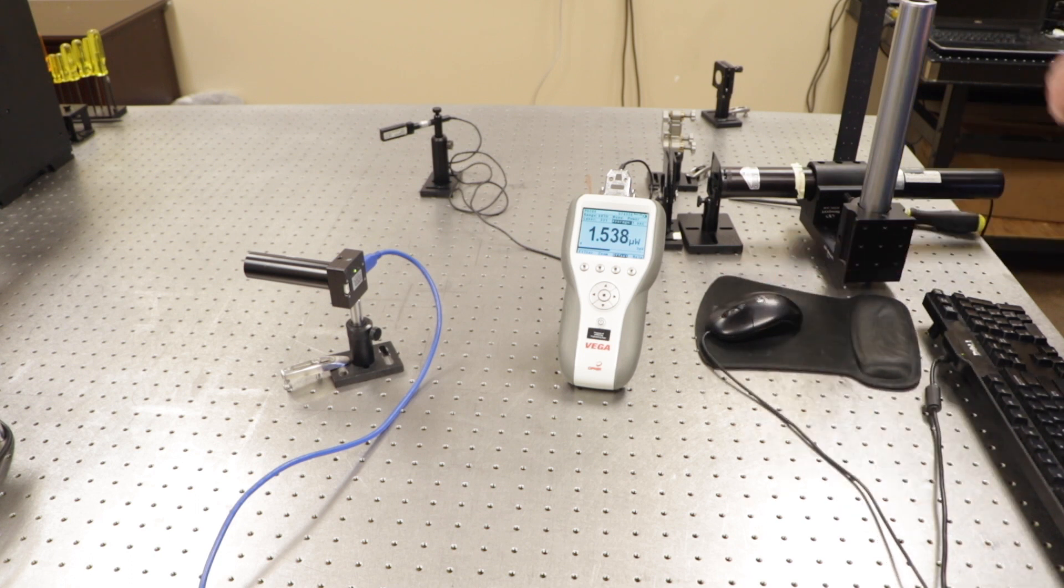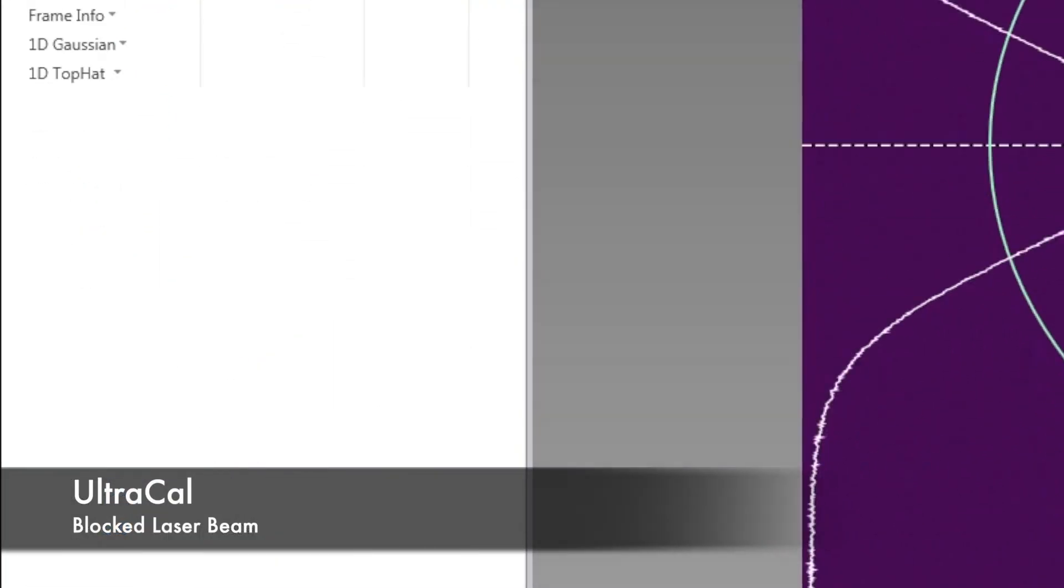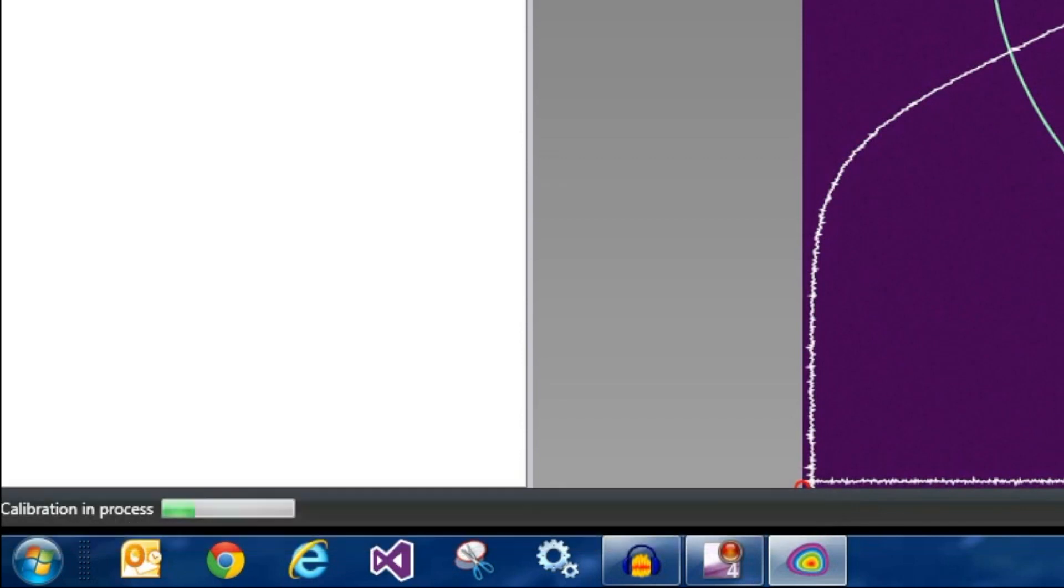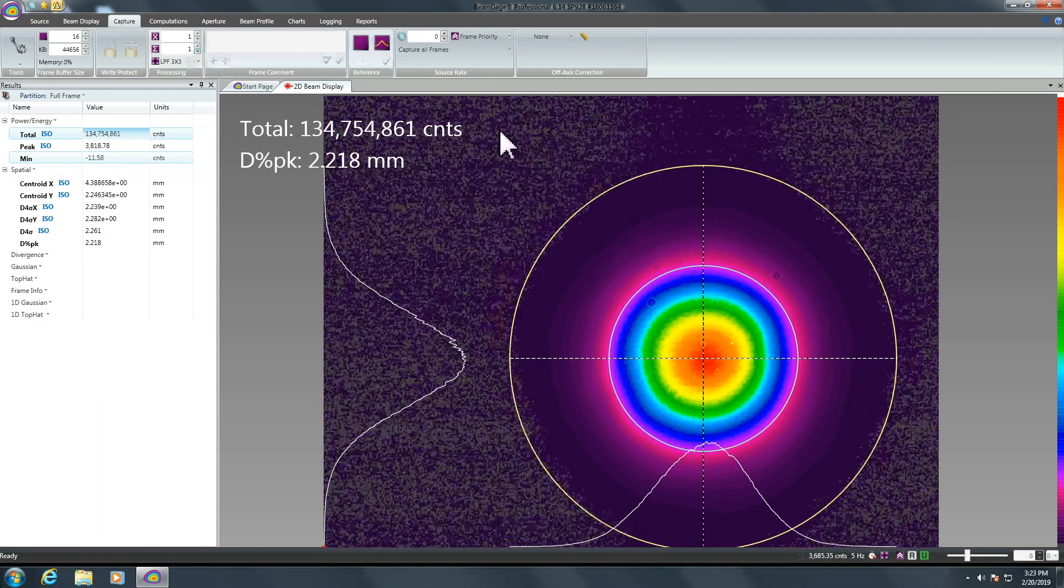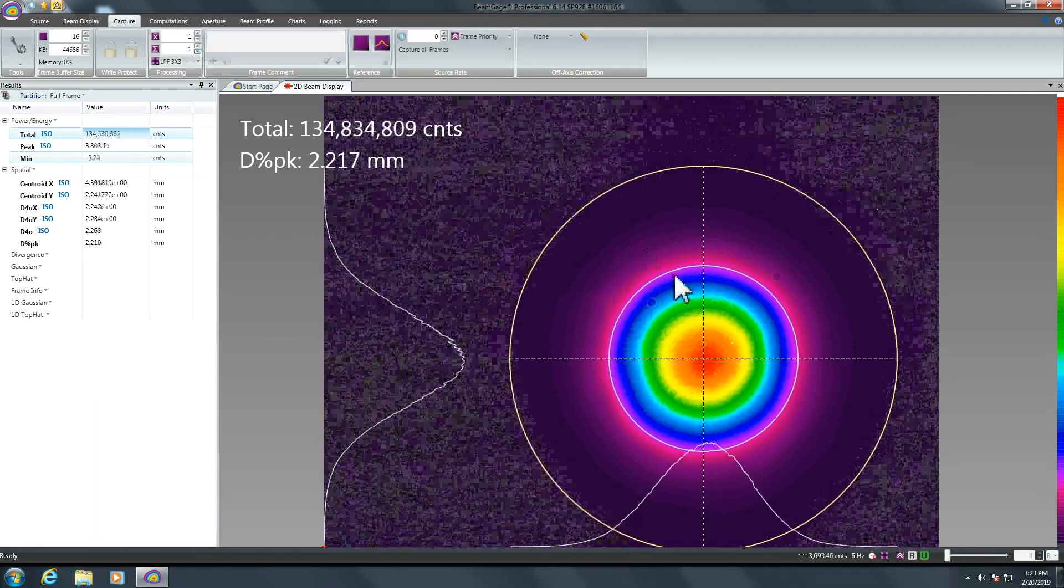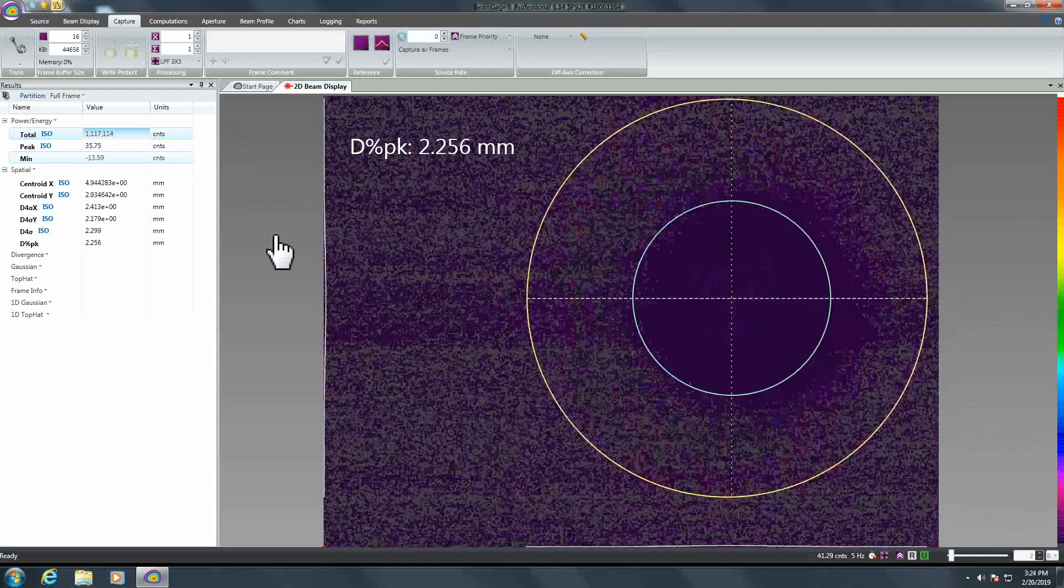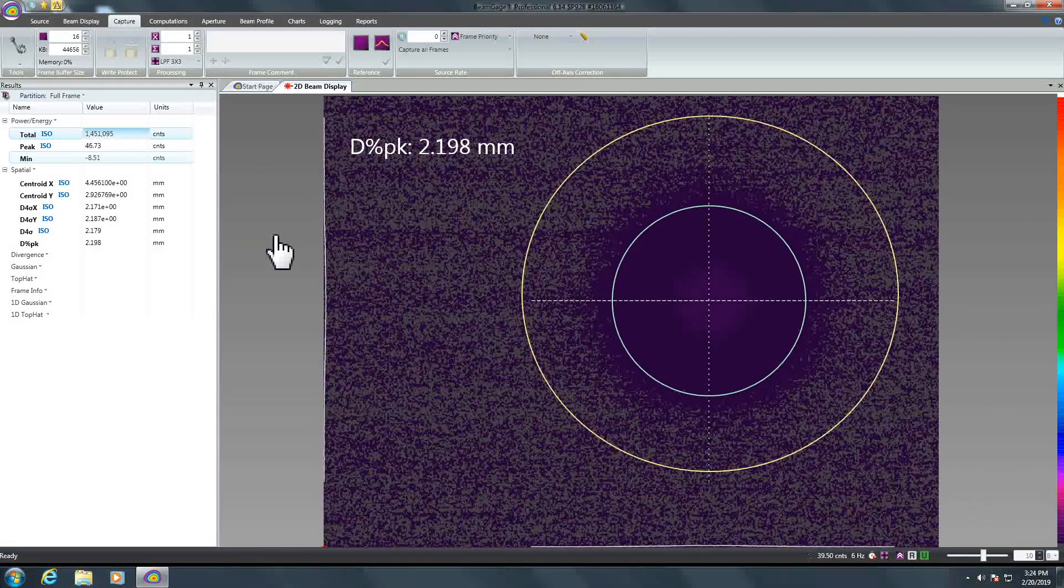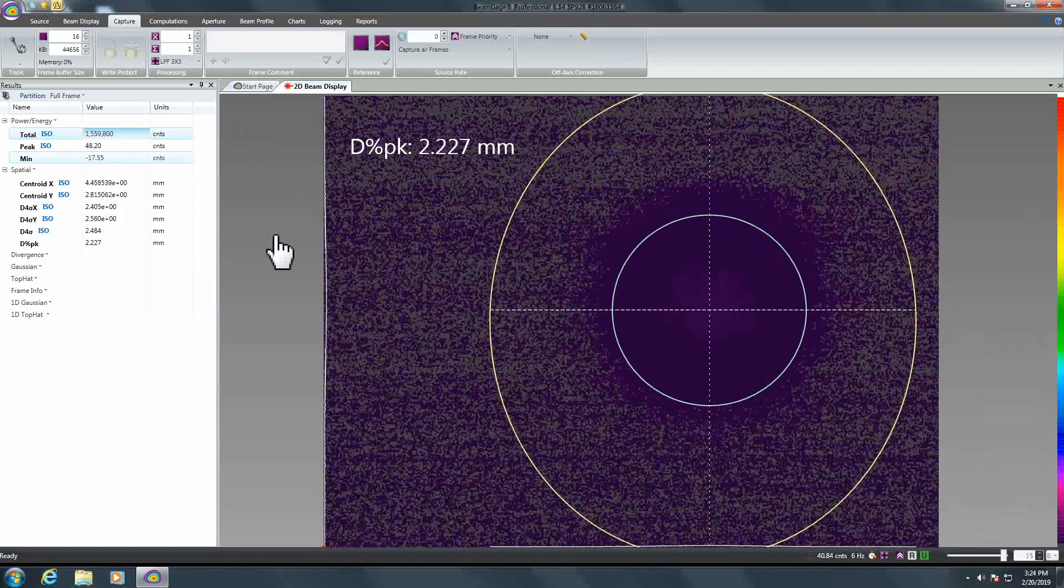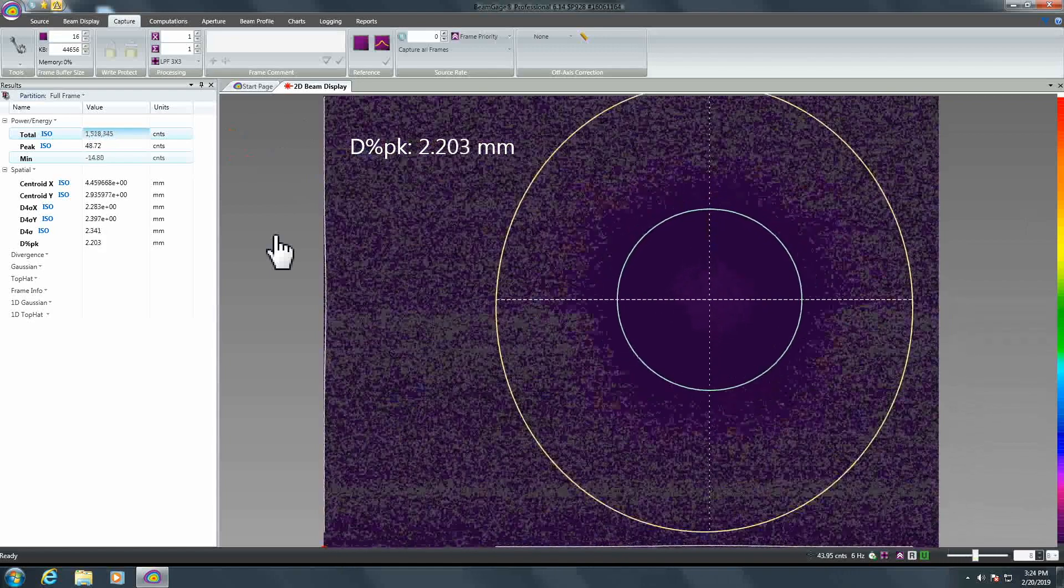We will now perform UltraCal on the camera with the beam blocked. When we remove the block, Beam Gauge measures the beam width at 2.2 millimeters. Moving the ND filters in front of the beam attenuates the laser energy by a factor of 100. The camera can barely detect the weak beam. Measuring the attenuated beam is difficult, as any noise in the system will overwhelm the weak beam.